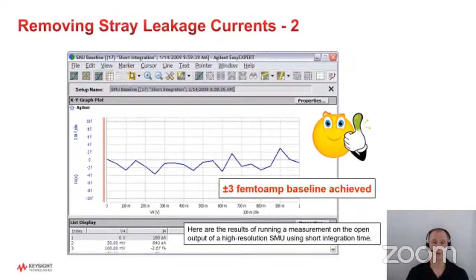This just shows an example graph measuring current versus time. This is an SMU measurement open, so there's nothing touching the SMU output. We've run the zero offset cancellation on it, however, and you can see, using just short integration, which means I'm integrating less than a power line cycle, so very little averaging is happening, that I can maintain a very low-level baseline of plus or minus about 3 femtoamps, which is typically what you would expect to see on precision or high-resolution SMUs if it's open circuit. So this is also one way you can verify whether your SMUs are working correctly.